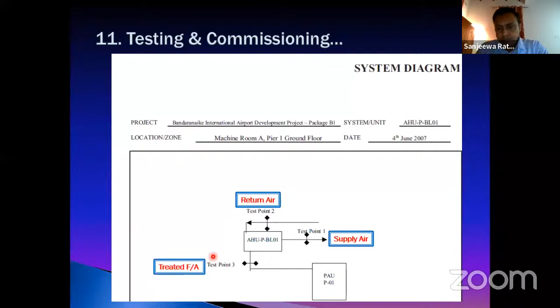So if you take this table, you will see this is for the AHU supply air, and the supply air duct size is given here as 1200 by 400. If it is 1200, it means it's quite a big duct. So they have taken 6 points to get the speeds of the airflow, and 4 heights. Altogether 6 by 4 means 24 points. They have taken the speed of the airflow and averaged it, and it is 7.03 meters per second, and this airflow rate is calculated as 12,148.